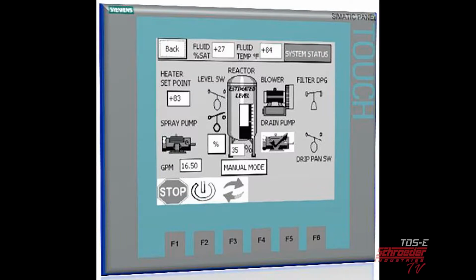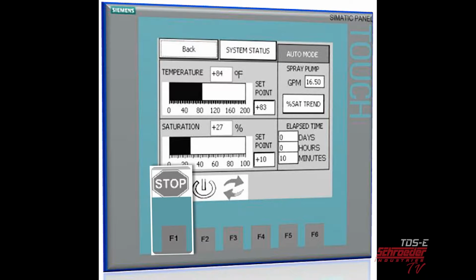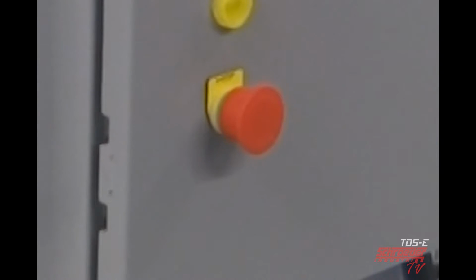The automatic mode system status screen can be accessed by pressing the system status button in the auto mode screen. This screen provides a summary of the inputs and outputs in the current status. Active outputs are highlighted by check marks. Please note, the F1 button is the stop button available on every screen. It will stop the spray pump immediately, but the drain pump will continue on for a short amount of time to empty the reaction chamber. Use the E-stop to shut down all pumps instantly in the event of a failure.